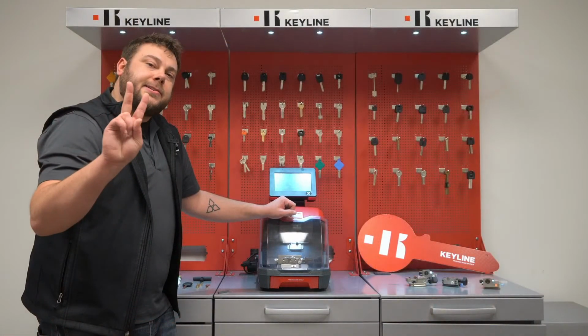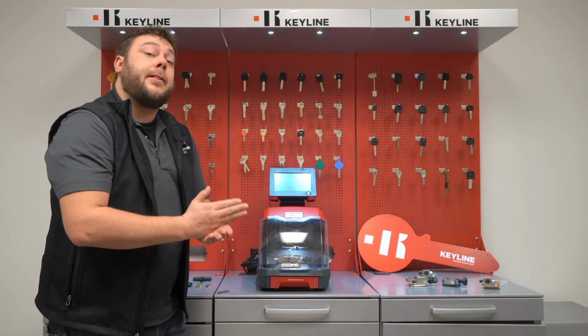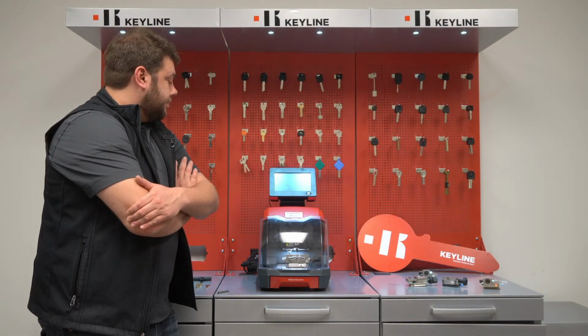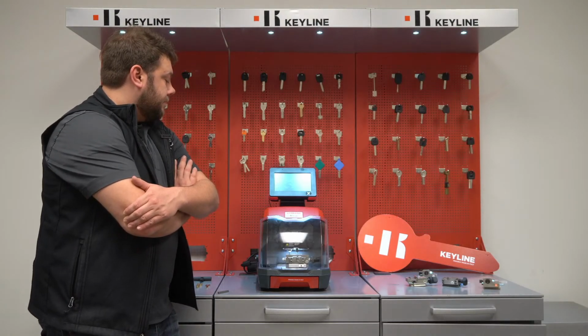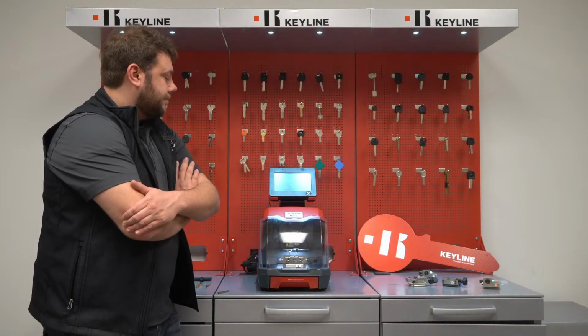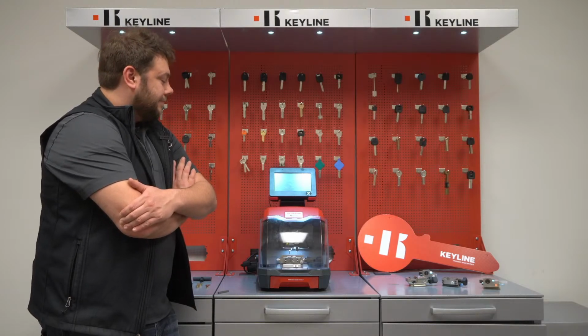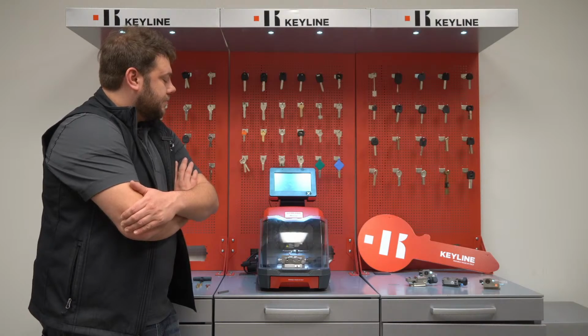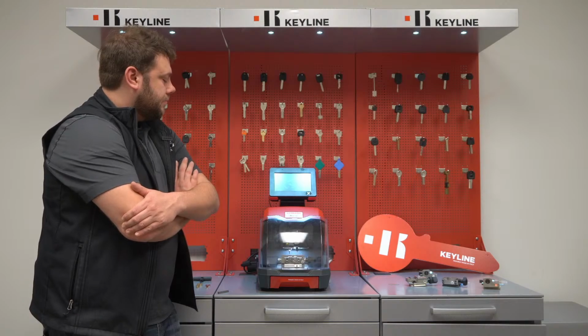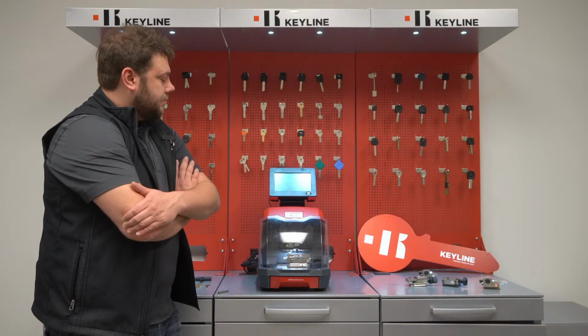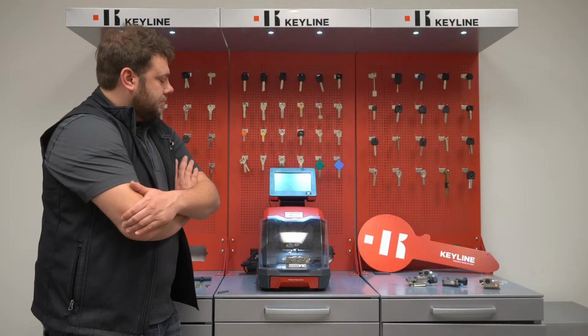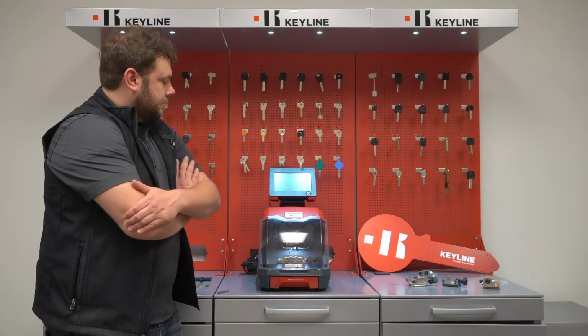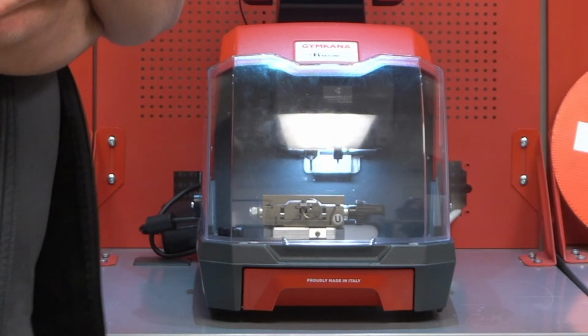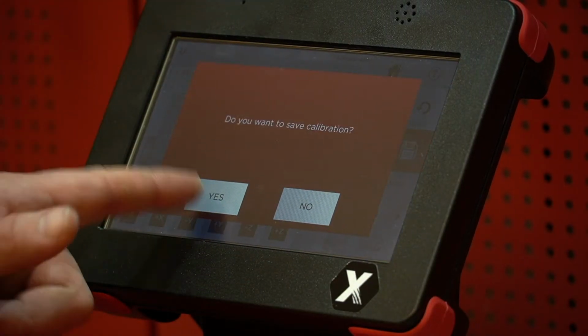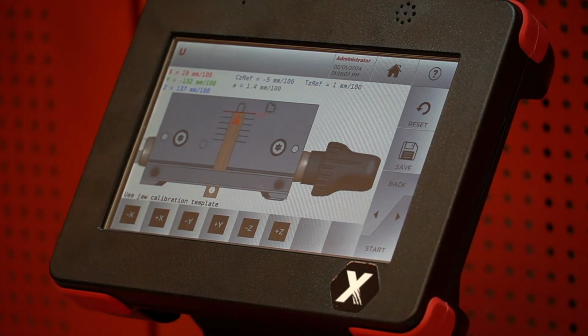Tracer setup, differential of plus or minus 2. Jaw setup, differential of plus or minus 4. And you are within tolerance of the calibration. Calibration complete. Please press save to apply the new values. You hit OK. Save. Yes. And our values are now within plus or minus 4 of our previous calibrations. So our jaw is now calibrated.